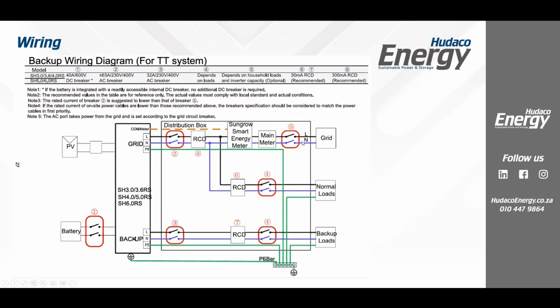Here's the grid. Here's your main incomer. Here's the main meter. Now in South Africa, most commonly what happens is we actually have the main meter outside on the grid side. This is where the utility, whether it's Eskom or City Power or City of Cape Town or whoever. Then inside the home, we've got a breaker. This is where we would recommend that you connect your CT. Then all of your normal loads, or in other words, what we call the non-essential loads, will come off after that. We do recommend putting in an RCD here, but sometimes it's not necessary if you're feeding straight in.